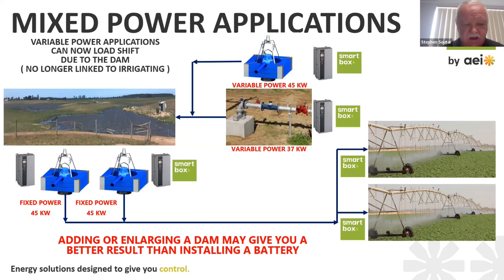Interestingly, even the ones that are fixed power, which is the one that pumps to the pivot, are fitted with variable speed drives, but that's so we can operate at a constant pressure at the pivot and optimise the energy used. But when it's running, the energy will pretty much be fixed.